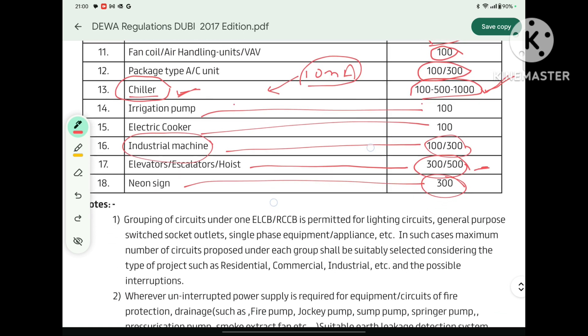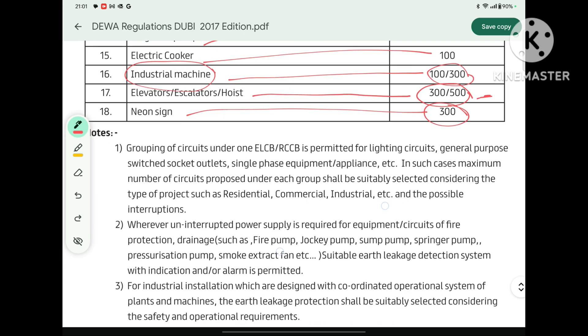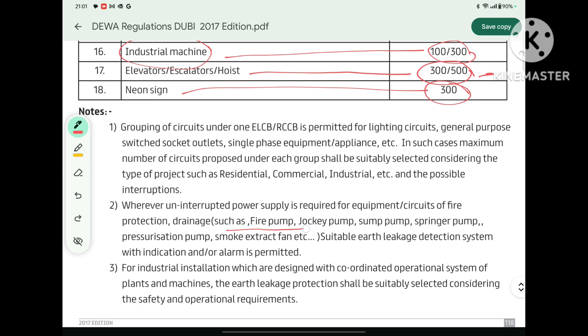For loads like fire pumps and jockey pumps, if there is a small leakage, it could trip the motor — and during a fire condition, tripping the fire pump would be a disaster, because the small leakage current is far less serious than the fire itself. Therefore, DEWA says that for such loads — fire pumps and jockey pumps — there should be a suitable earth leakage detection system with alarm. If there is leakage, it will give an alarm but will not trip the system, avoiding disaster during fire conditions.